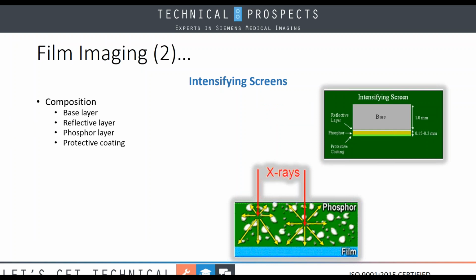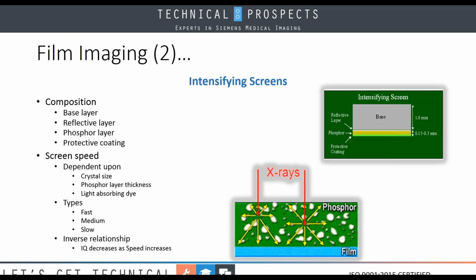Moving on here, the biggest advancement though was the intensifying screens. And here we look at the composition of the intensifying screens that are made up of a base layer, a reflective layer, the heart and soul, the phosphor layer, and lastly, a protective coating. Now the phosphor layer, the biggest thing here is this is what's going to set up the screen speed. All right, this is dependent upon the size of the crystals. Now, as time has gone on, the crystals today are more uniform because we use more of a man-made type crystal. However, back in the early days, we used chunks of crystals and they were different sizes. So this would also determine the amount of light being emitted from the screen.